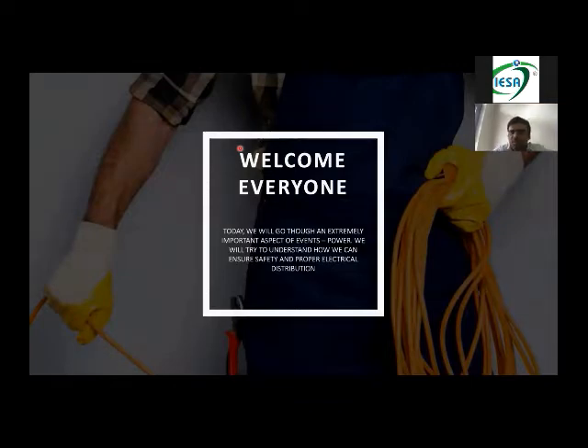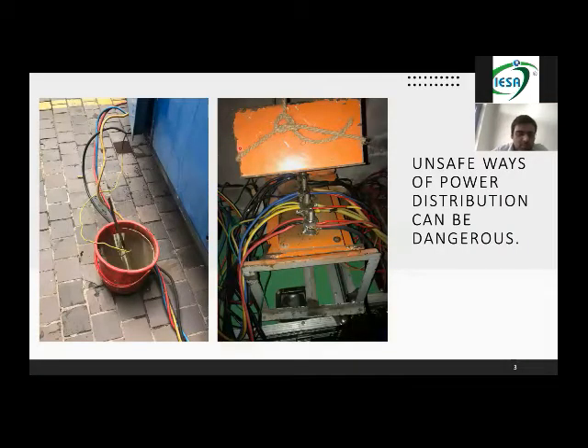Okay. So again, I'll show you some disturbing pictures from site. What you see: open boxes, loose ends, a bucket earth. When we are working in an exhibition hall, the power is given to us by the venues. But when we are doing outdoor shows, this is a very normal scenario, what you see on sites, that an open box is coming. This happens when you're taking a genset and your cabling is free, you're getting 50 meters of cable free. So this is what actually free looks like.